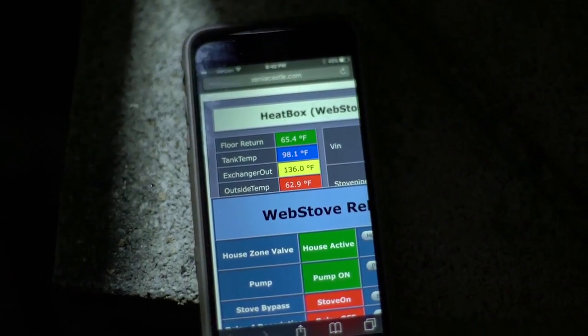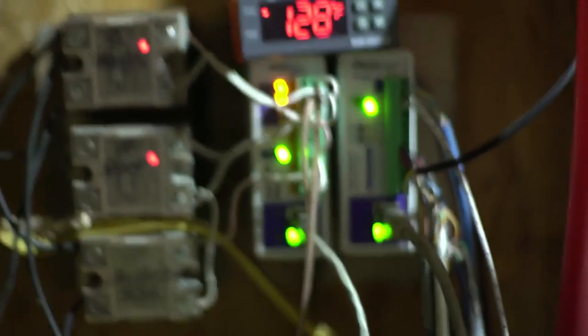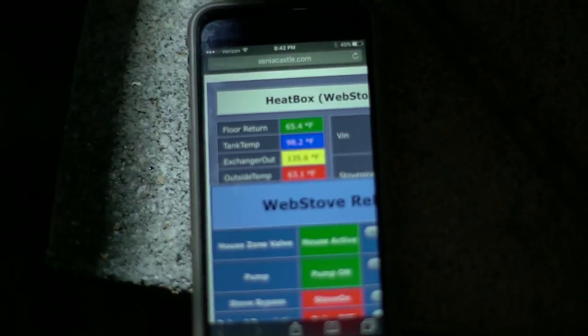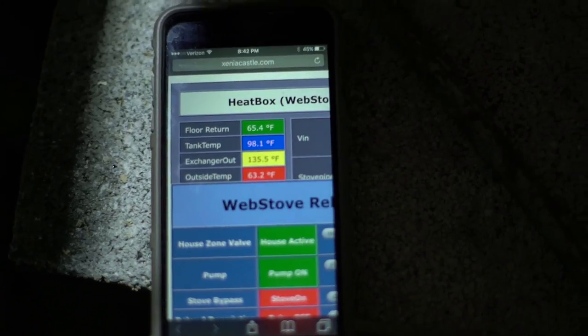This gauge right here, temperature sensor, is off a few degrees. I'll switch over to the phone. So the exchanger, you'll see when I get this focused, is cooling off. It's at 136 right now, and there's a little bit of a difference between what it reads here and the actual calibrated sensor.